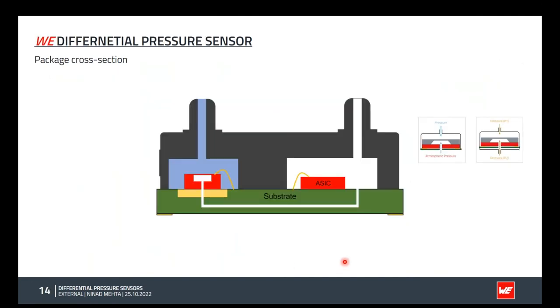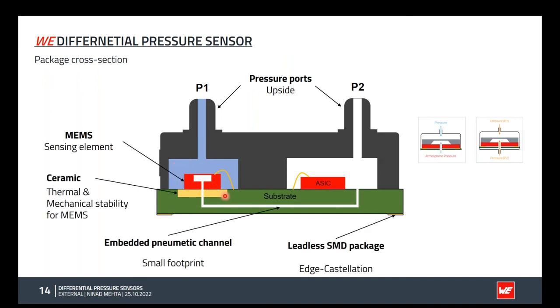Let's have a look at the cross section of the differential pressure sensor. How does it look? In the standard product, we have two ports on the top side. Port one connects directly to the top side of the MEMS element, and the MEMS element is directly placed on a ceramic so that it provides better thermal and mechanical stability, and thus better offset performance. And the other side of the MEMS element is connected through a hole via an embedded pneumatic channel to the other port, and the MEMS and ASIC are then bonded to the PCB. So in the end, we have a leadless SMD package, so you can also do hand soldering if required for prototyping.